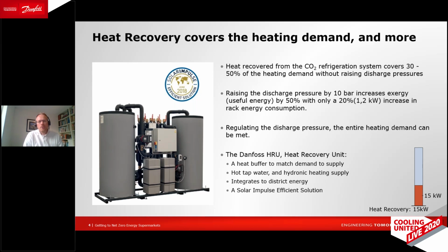Of course, this depends on where you are in the world. In the more northern latitudes you will have a higher heating demand, and in southern latitudes, lower heating demand. So there is a range, of course. But our experience shows that wherever we are, if we can tweak the system a little bit, then we can also cover the full demand. For example, in this case, we could raise the discharge pressure by about 10 bar, and by doing so, increase the useful energy by 50%. This is roughly a 15 to 20% increase in the rack energy consumption, but this is very low compared to the amount of heat that we get out.